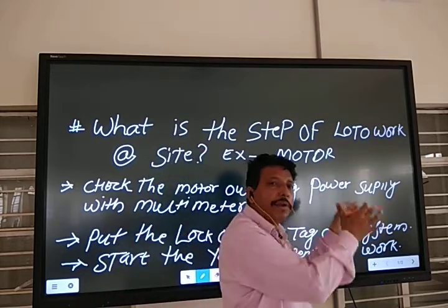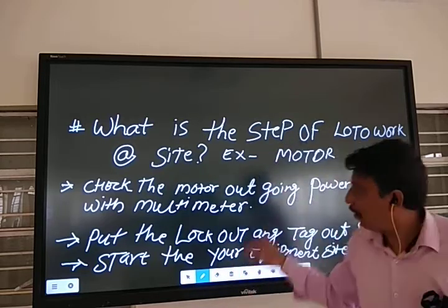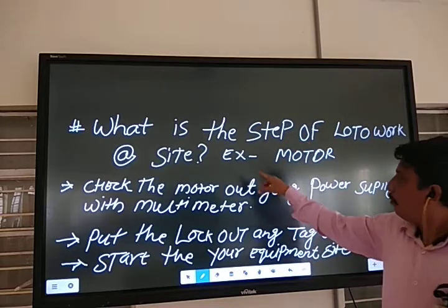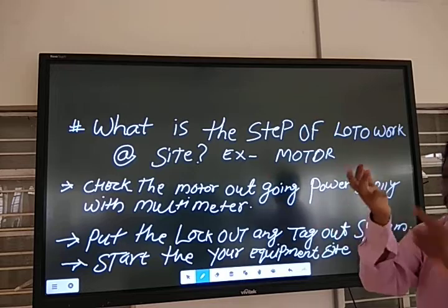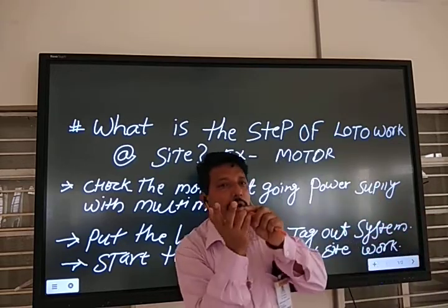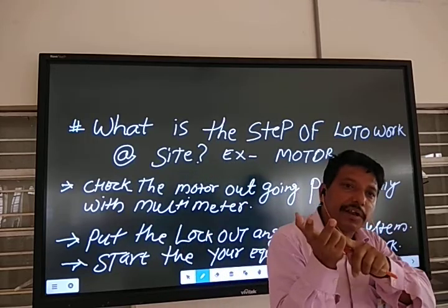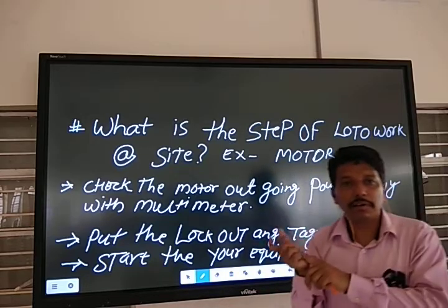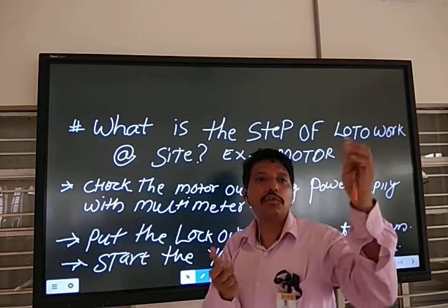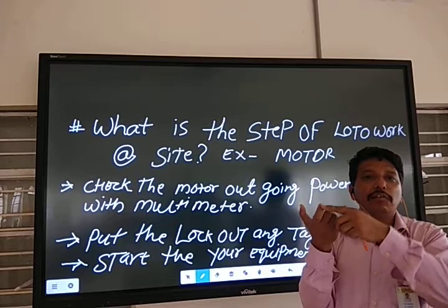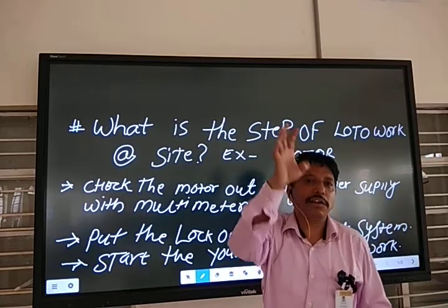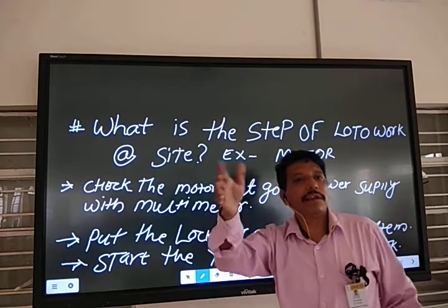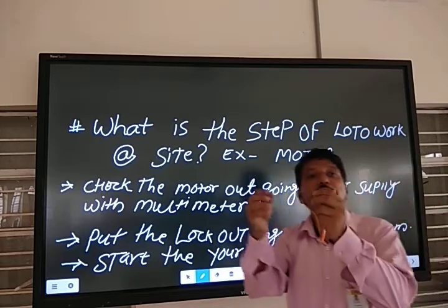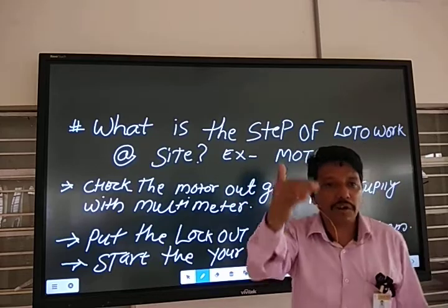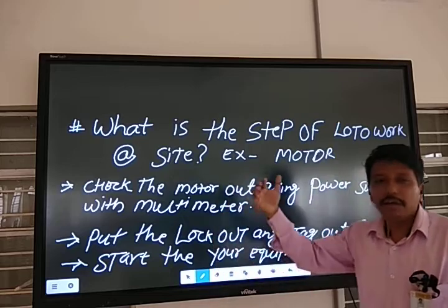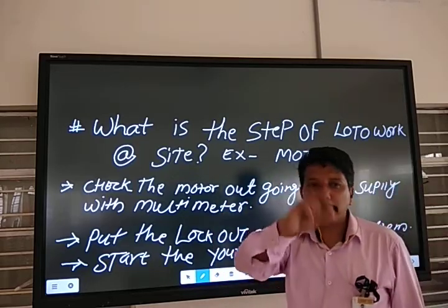If you touch or maintain any equipment, first take lockout training and follow the step by step rules. First you need a permit. Second, you need the drawing for the motor or whatever you want to maintain. Next is notice to the affected person. Then switch off the main incomer where the power supply comes in: go there with your drawing, check it, and stop the power supply. Then confirm by checking with the multimeter again whether there is current or voltage. If not, this means the correct breaker is off.